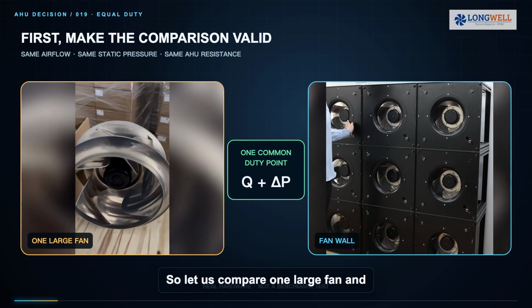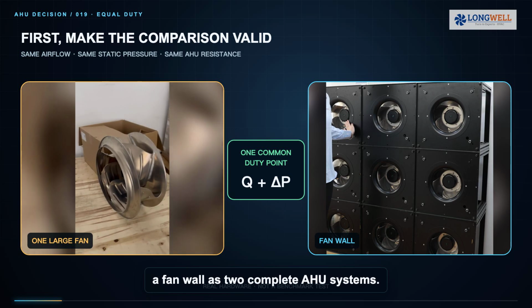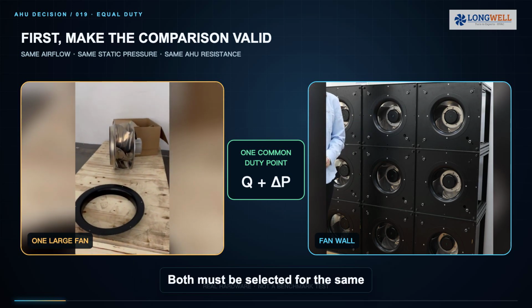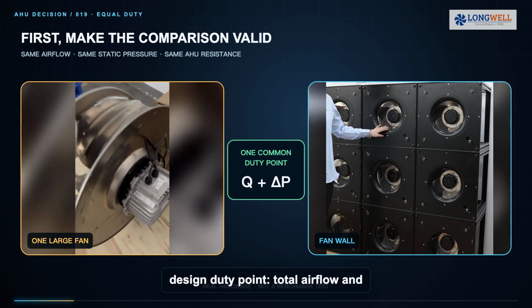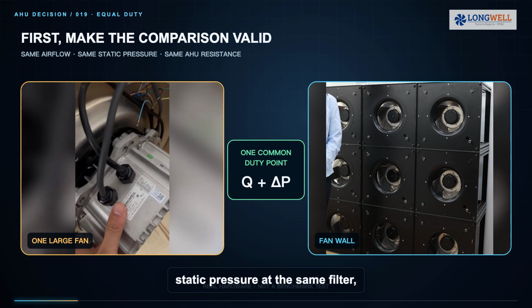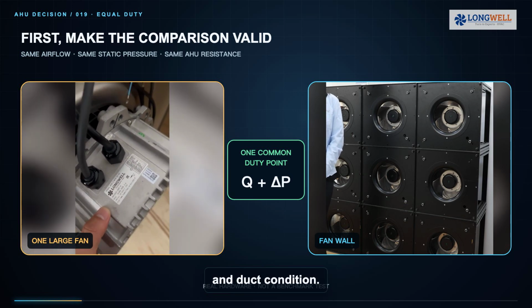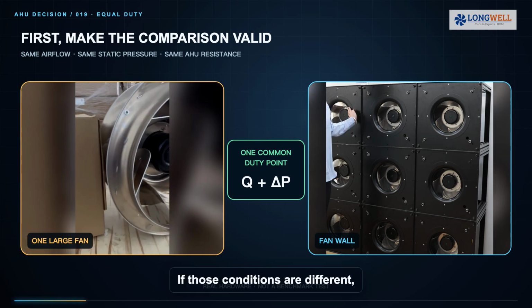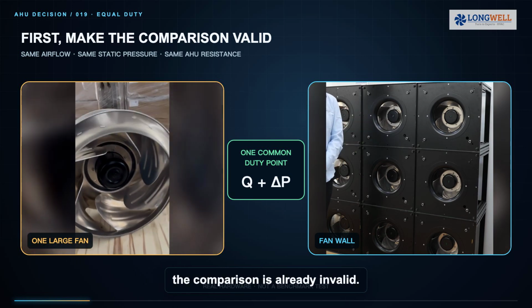So let us compare one large fan and a fan wall as two complete AHU systems. Both must be selected for the same design duty point, total airflow and static pressure at the same filter, coil, damper, plenum, and duct condition. If those conditions are different, the comparison is already invalid.